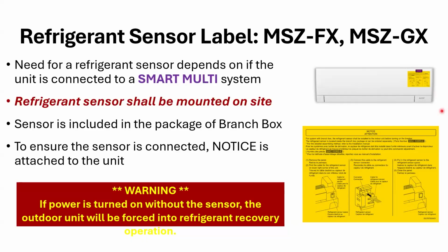So again, this yellow label, if you read what it says: for a system with a branch box, the refrigerant sensor shall be installed to the indoor unit before turning on the breaker. The refrigerant sensor is located inside the branch box or can be ordered separately. It gives you a part number. For the detailed assembly method, refer to the install manual. This is just a quick little picture of it, but we have some more information on how to install it coming up.